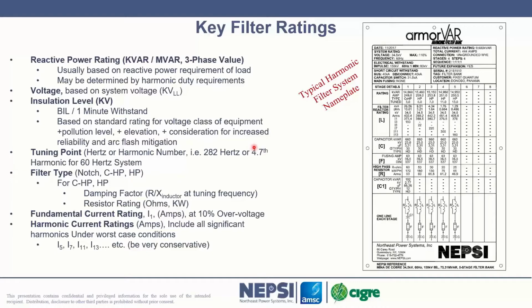So damping factor is a very important parameter when defining C-high pass and high pass type filters. Generally speaking, as you go to a lower value of damping factor, you're increasing the kW, you're decreasing the ohms, and as a result, you're increasing the cost of the filter. So we're going to be talking about the resistor in a few minutes. And then, of course, fundamental current rating.